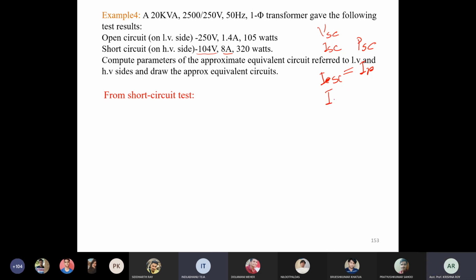So calculate IRH, that is high voltage side current. Short circuit test is performed on the high voltage side. So IRH, rated current of high voltage side, calculate this, 20 into 10 to the power 3 divided by 2500 ampere. Calculate this. 8 ampere. If it is 8 ampere, then this ISC is equal to IR. Otherwise, you have to calculate this copper loss at rated current by simply applying unitary method.